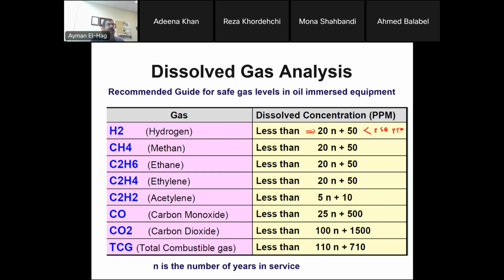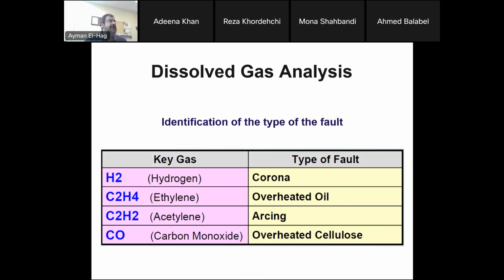And now with the development in communication systems, in the SCADA system, people can see actually what is happening in the station, the substation, or the monitoring station, where you can see in real time for what transformer, what is the dissolved gas analysis. Now these gases reflect certain types of problems. For example, H2 is corona or partial discharge, C2H4 is overheated oil, C2H2 is arcing, and CO is when we have overheated cellulose.